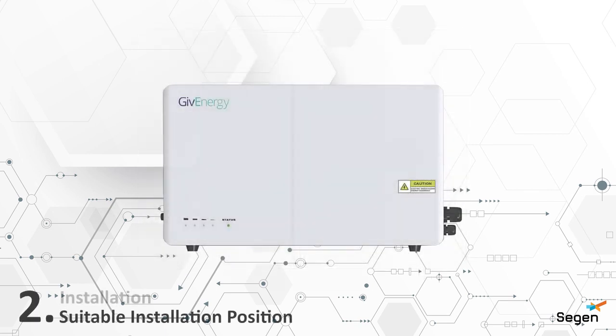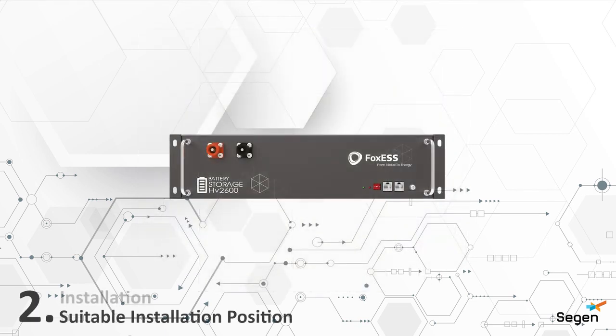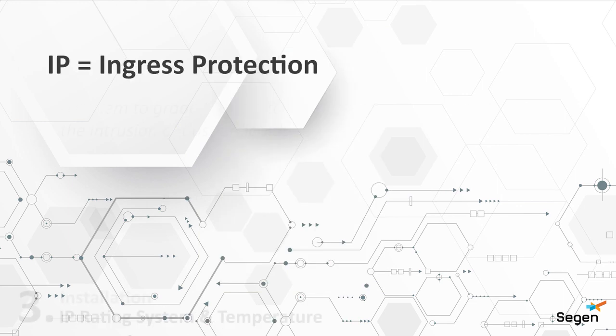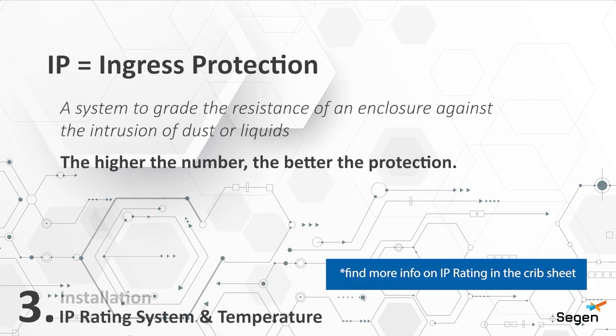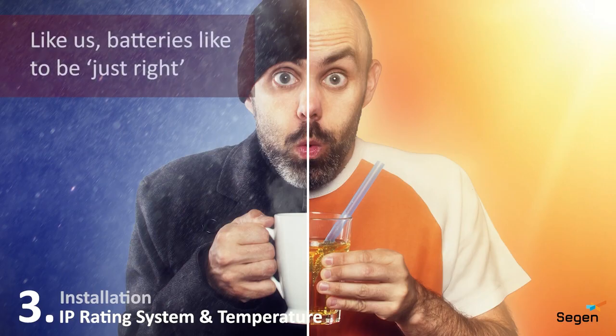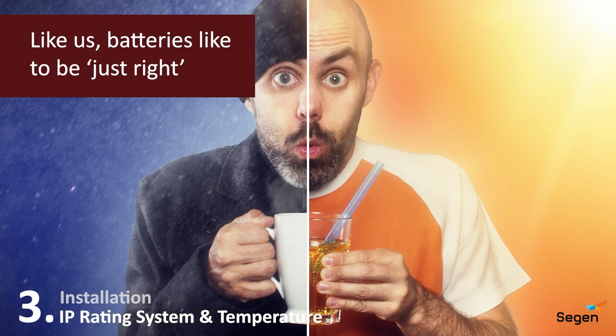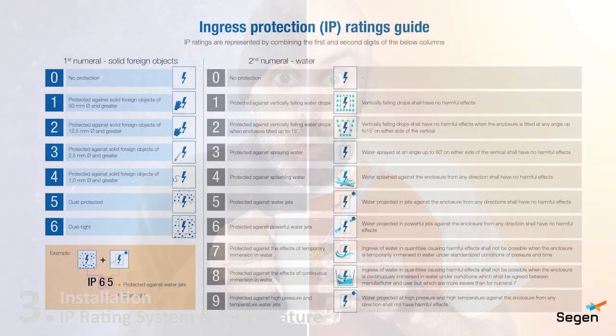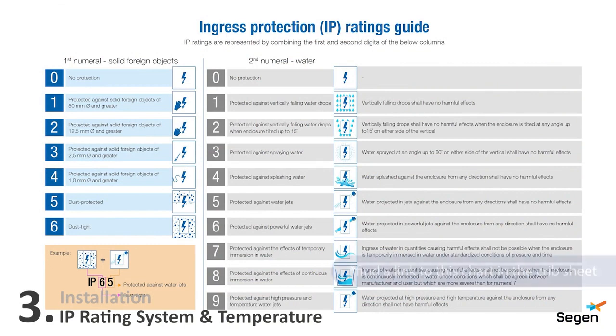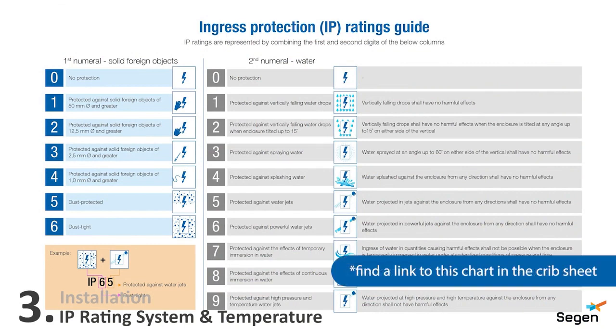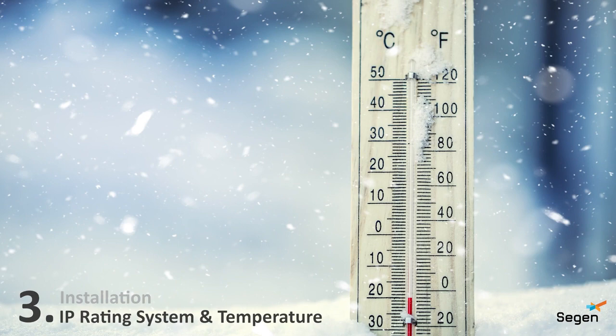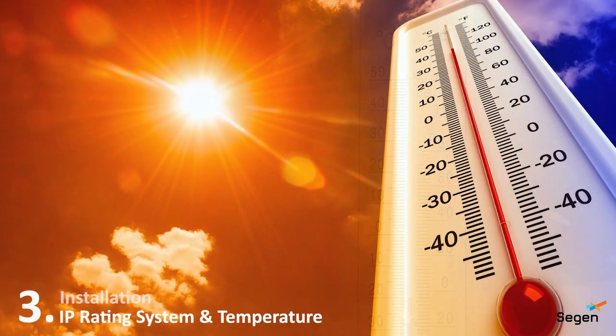Batteries come in a range of shapes and sizes, and choosing a suitable place to install is essential. While some battery solutions are IP rated for outdoor installation, batteries have an ideal operating temperature which should be observed. In addition, even though a battery might be IP rated for installation outside, manuals will ask the installer to choose a sheltered position, keeping the equipment away from the direct effects of extreme weather. Also, loft spaces and uninsulated external garages can reach extreme temperatures, so may not always be ideal.